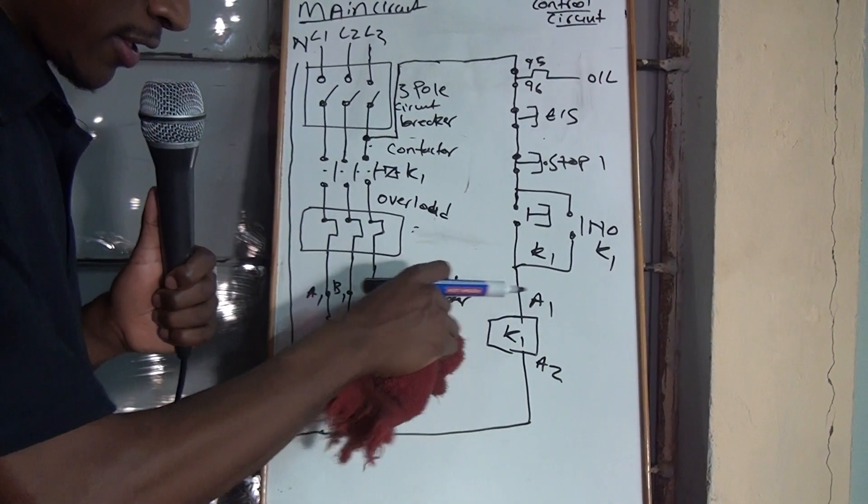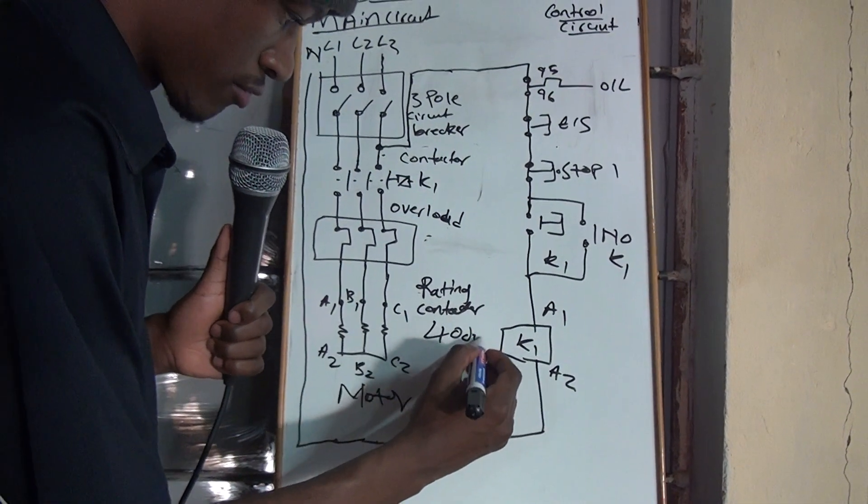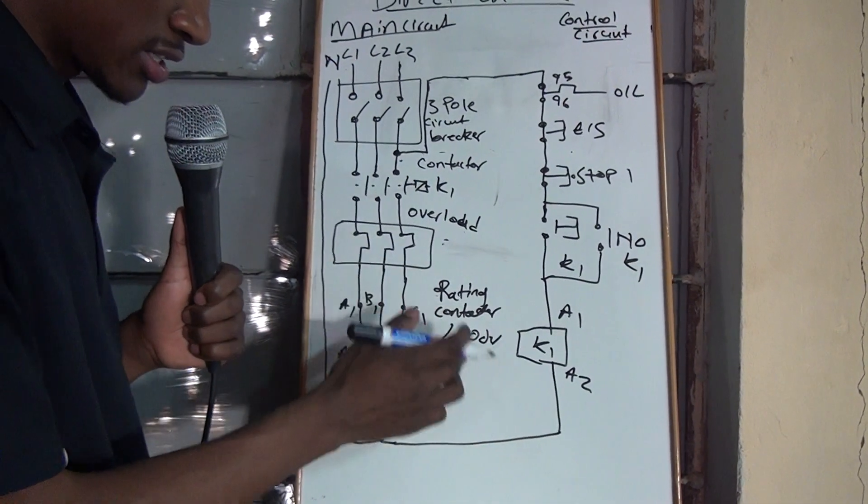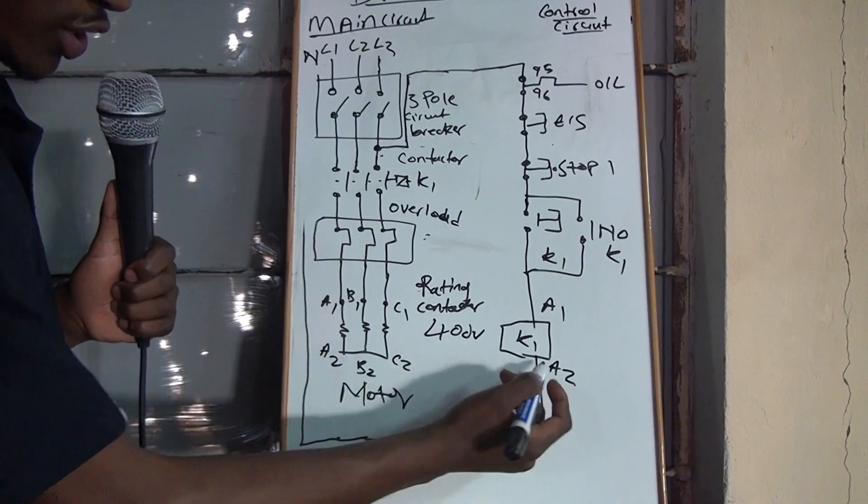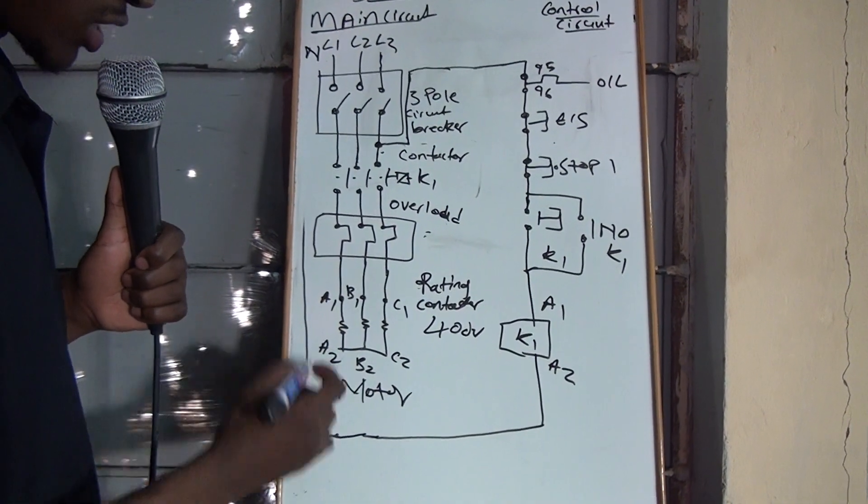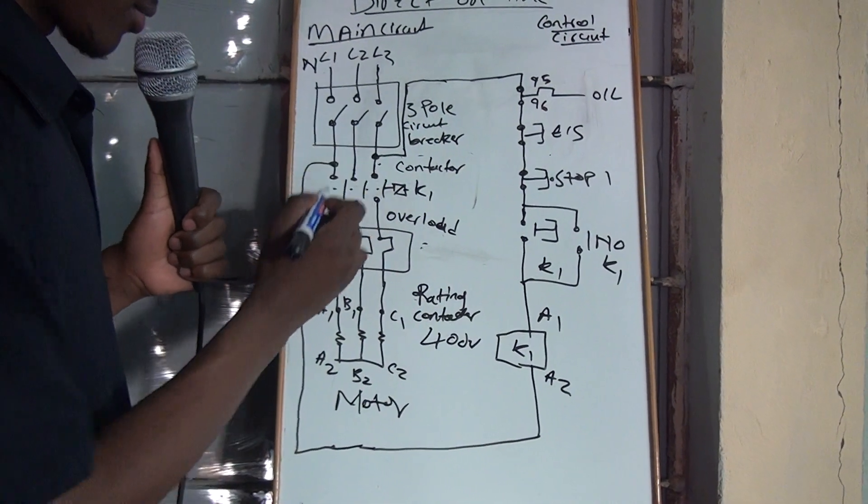But from 400 volts, if the contactor rating is 400 volts, then now, you no longer connect your A2 on the neutral. You connect it on one of the lines.